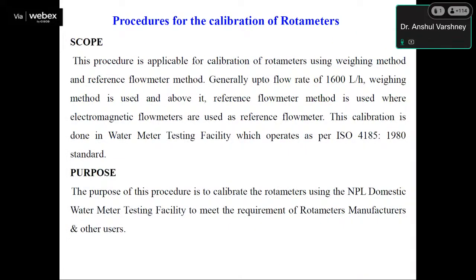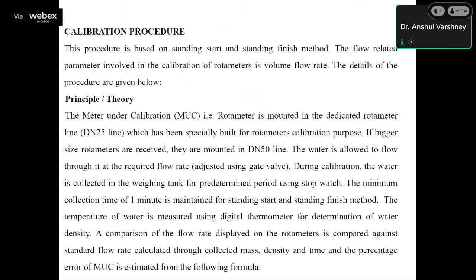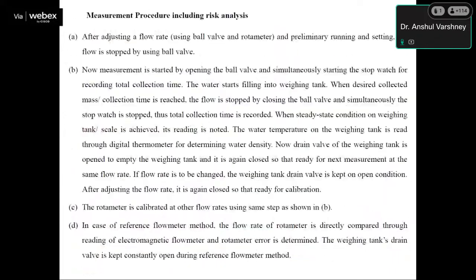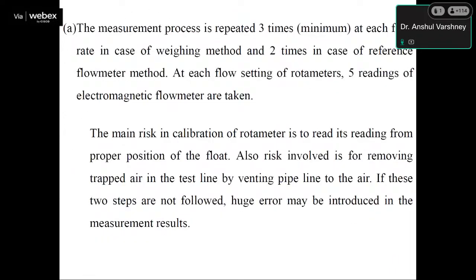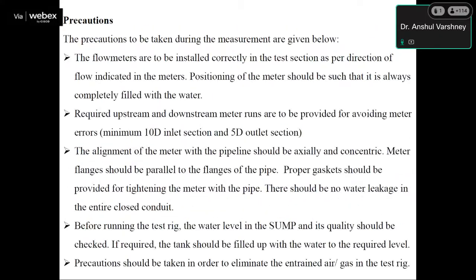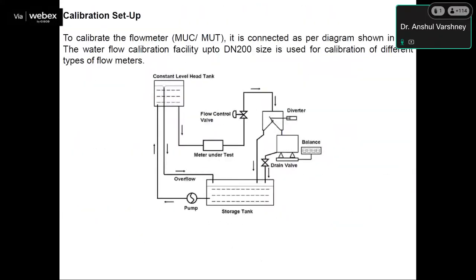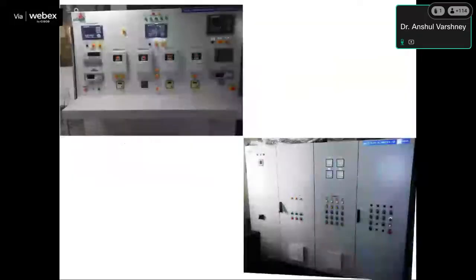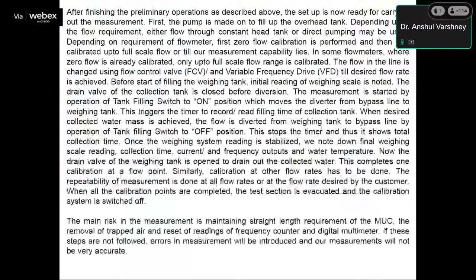Basically, these are the calibration procedures for rotameters and mass flow meters. We are using the gravimetric method for calibration of all these types of flow meters. For rotameters, we are using the standing start and standing finish method, and for other flow meters like mass flow meters, magnetic flow meters, and turbine and vortex flow meters, we are using the flying start and flying finish method. In addition to this, we also have a gas flow calibration facility.